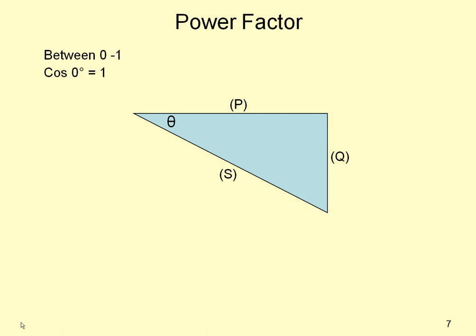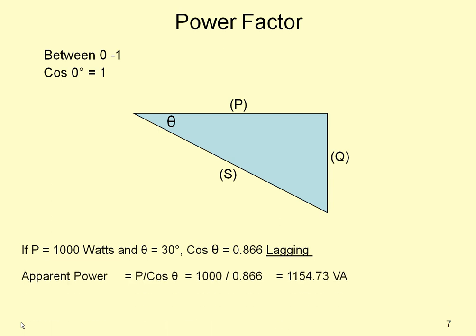The power factor is very important. It will always lie between 0 and 1, so the cosine of 0 degrees is 1. Taking an example, if the power is 1000 watts and theta is 30 degrees, the cosine of theta would be 0.866 lagging. The apparent power would be 1000 watts divided by 0.866, so we have 1154 VA.